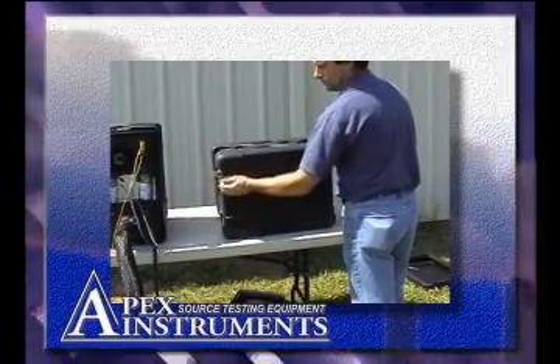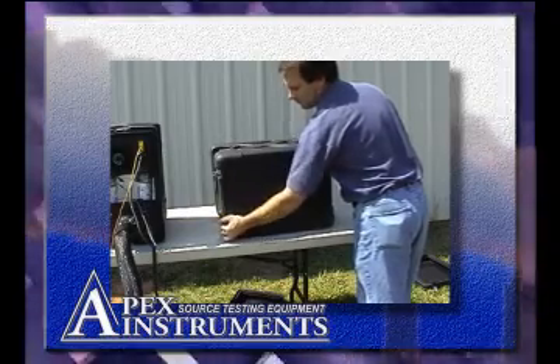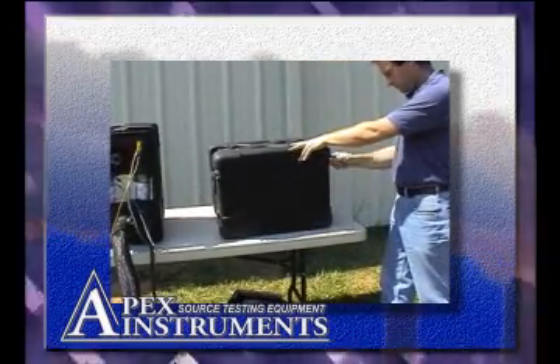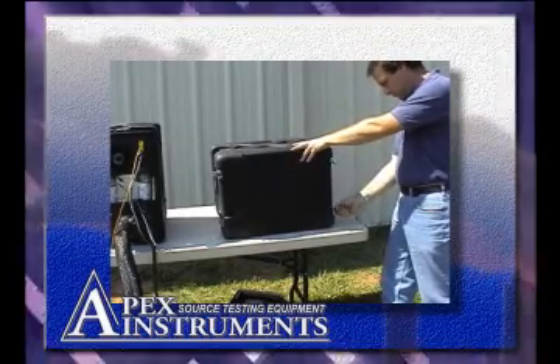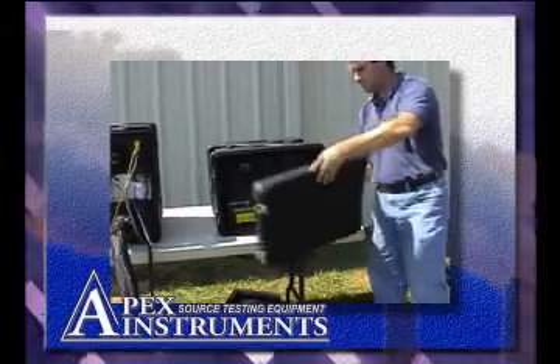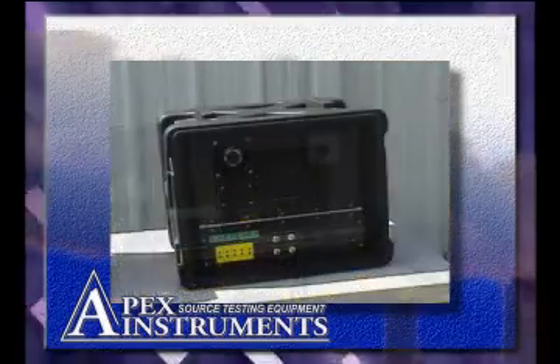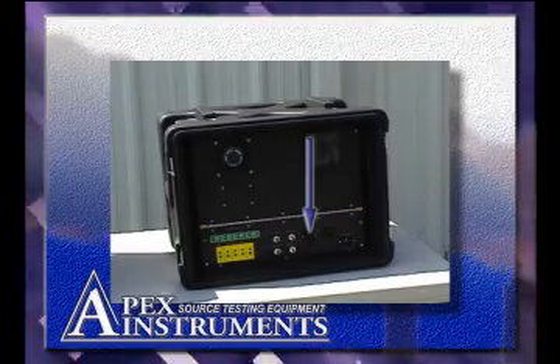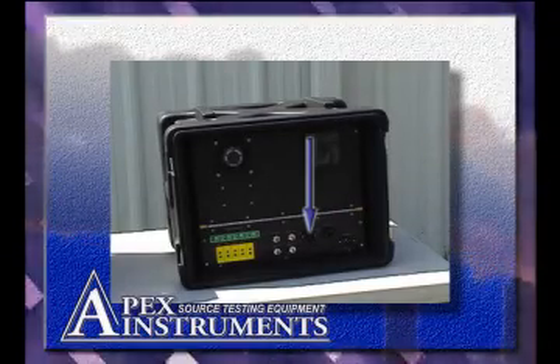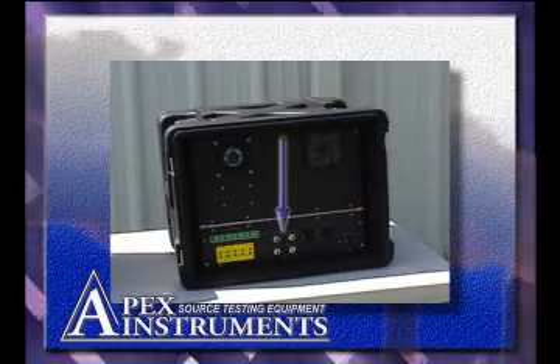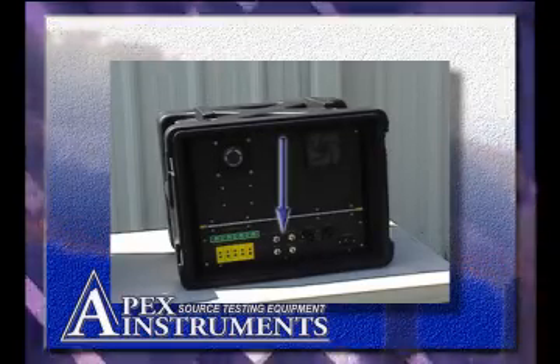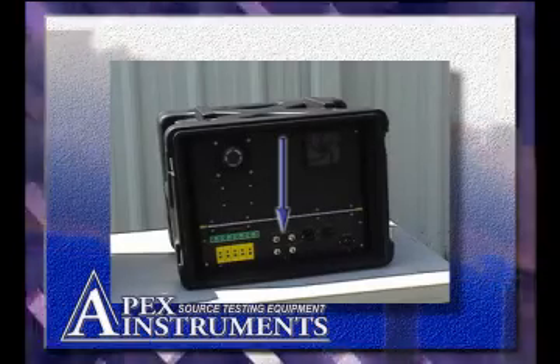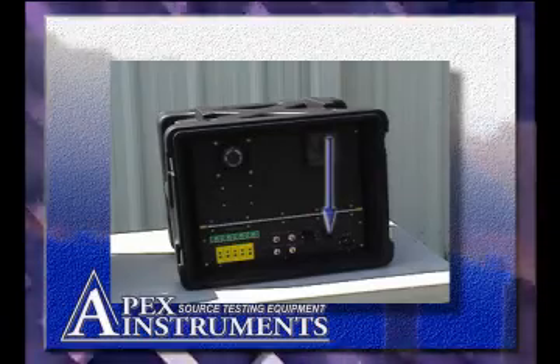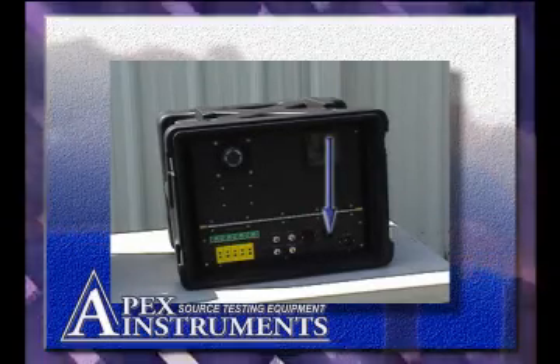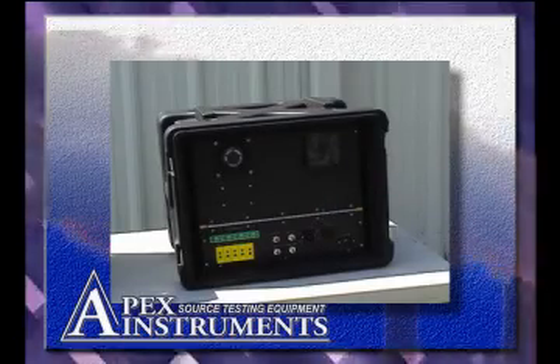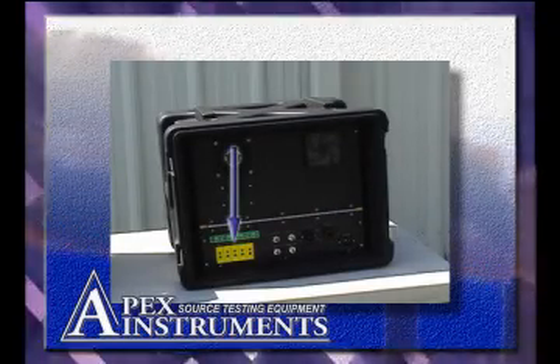Next, remove the rear cover to provide access to the console input connections. The probe heater power connector is located to the left of the main AC power connection. To the left, the operator will see the sample line input ports, and next to those are input ports for optional pitot inputs. There is a wide area network Ethernet connection that can be used to connect the console to the facility network. To the far left are the thermocouple connections.